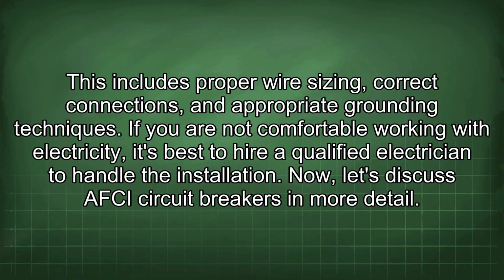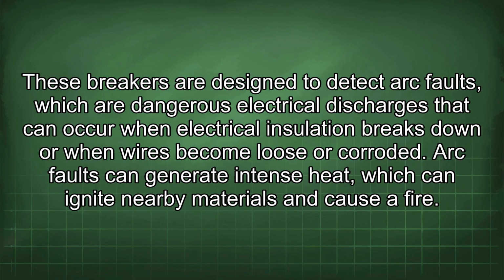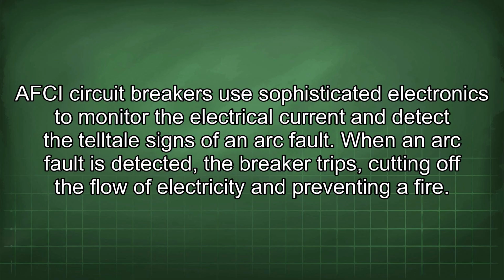Now, let's discuss AFCI circuit breakers in more detail. These breakers are designed to detect arc faults, which are dangerous electrical discharges that can occur when electrical insulation breaks down or when wires become loose or corroded. Arc faults can generate intense heat, which can ignite nearby materials and cause a fire. AFCI circuit breakers use sophisticated electronics to monitor the electrical current and detect the telltale signs of an arc fault. When an arc fault is detected, the breaker trips, cutting off the flow of electricity and preventing a fire.